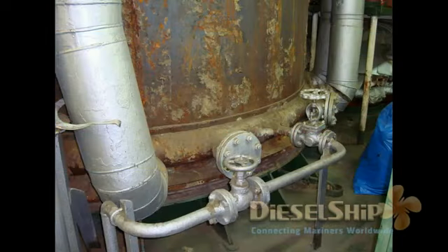So here are some pictures of boilers which I worked on. The boiler shown over here is completely ripped off. We were doing some retubing work with some Greek fitters, so this picture was taken at that time. Let me explain some components which are visible in this picture. This is the water ring, and these are the downcomers. What do you see over here? These come from the steam and water drum, and the downcomer brings the cold water to this water ring.